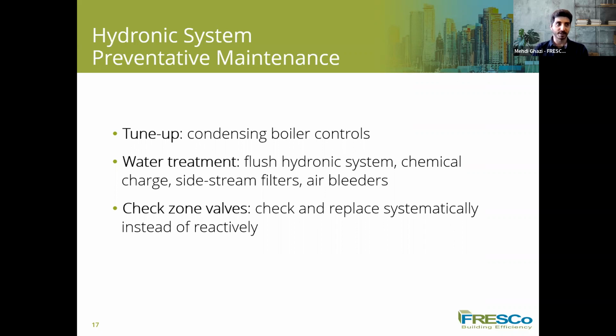Again, from experience, when I was working in a hotel which had more than 500 rooms, because there was no plan when I joined, every day it was part of the maintenance team's job to replace 2-3 zone valves or zone valve motors, because there was no plan for replacing them periodically and systematically, which was leading to a lot of complaints from the guests.